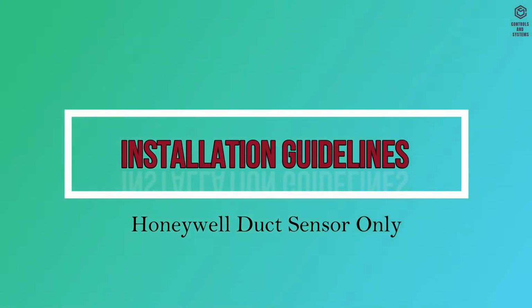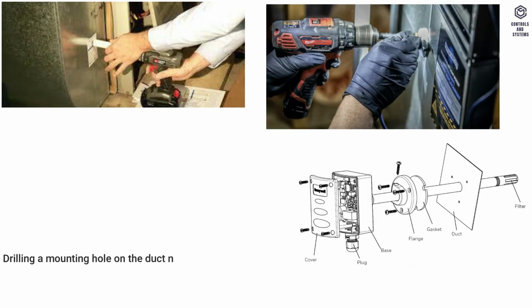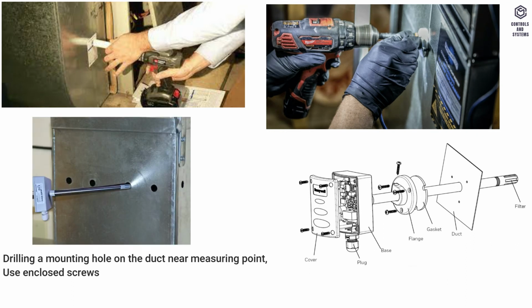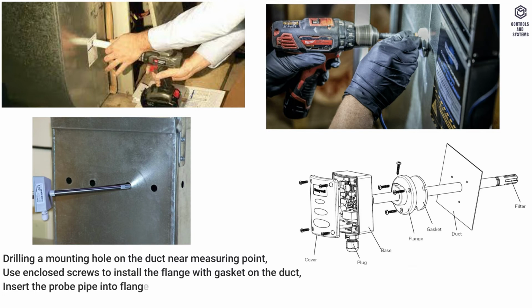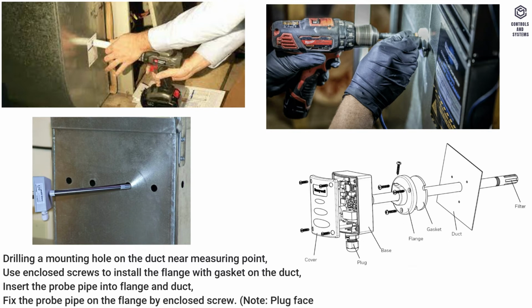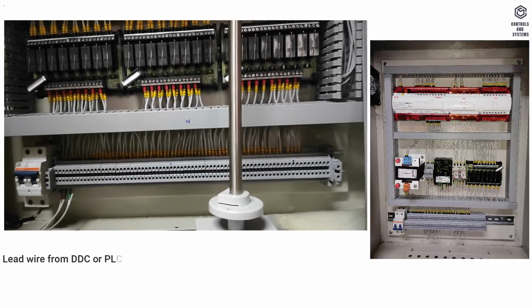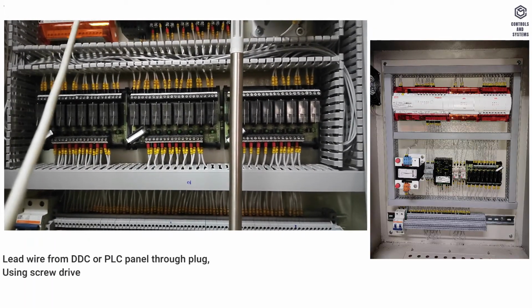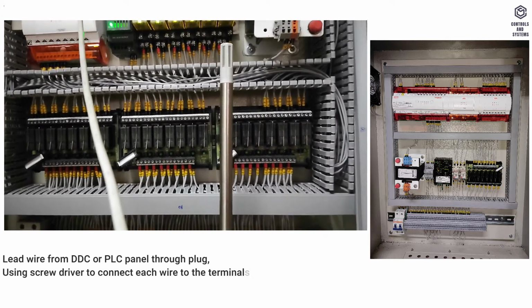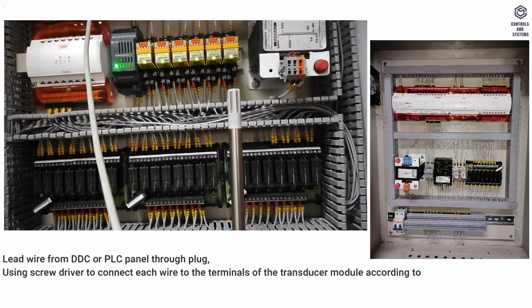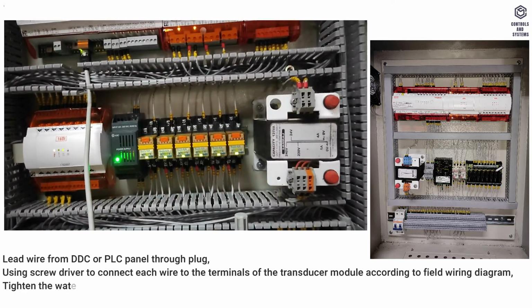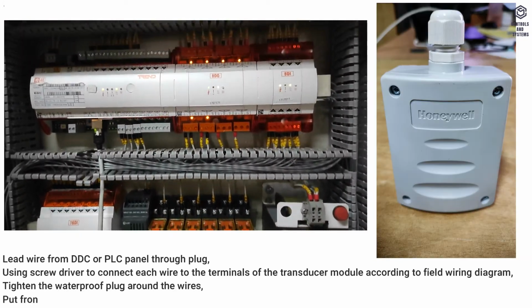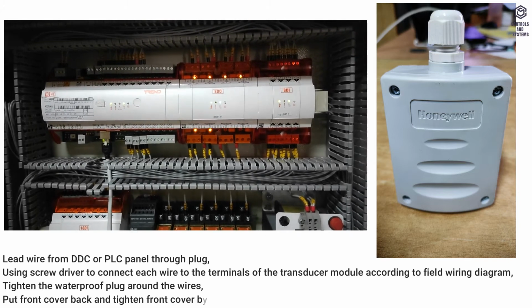Installation guidelines. Drill a mounting hole on the duct near the measuring point. Using the enclosed screws, install the flange with gasket on the duct. Insert the probe pipe into the flange and duct. Fix the probe pipe on the flange with the enclosed screw. Note: plug faces the bottom direction. Lead the wire from the DDC or PLC panel through the plug, using a screwdriver to connect each wire to the terminals of the transducer module according to the field wiring diagram. Tighten the waterproof plug around the wires, put the front cover back and tighten.